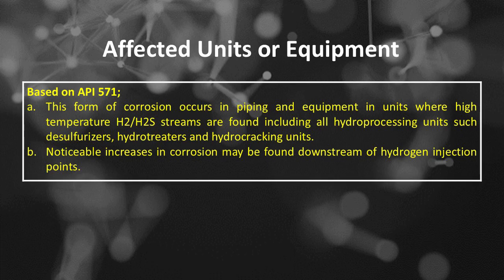High-temperature hydrogen or H2 and hydrogen sulfide or H2S corrosion affected units or equipment based on API 571. Number A. This form of corrosion occurs in piping and equipment in units where high-temperature hydrogen or H2 and hydrogen sulfide or H2S streams are found, including all hydroprocessing units such as desulfurizers, hydrotreaters, and hydrocracking units. Number B. Noticeable increases in corrosion may be found downstream of hydrogen injection points.